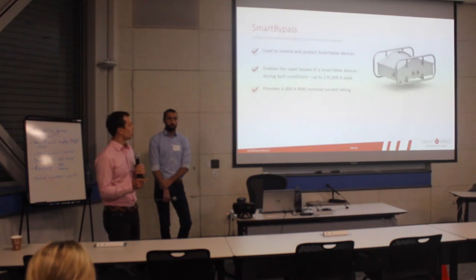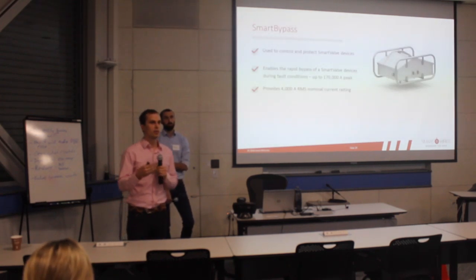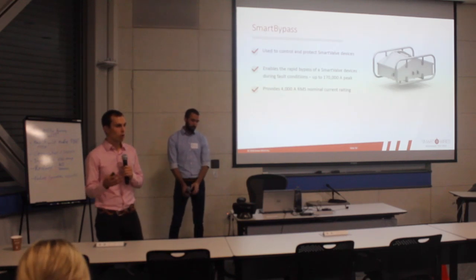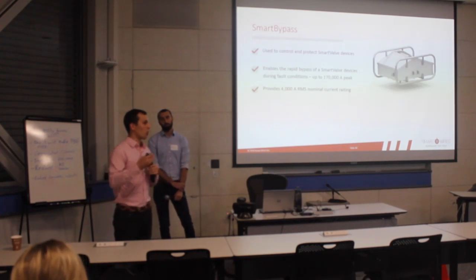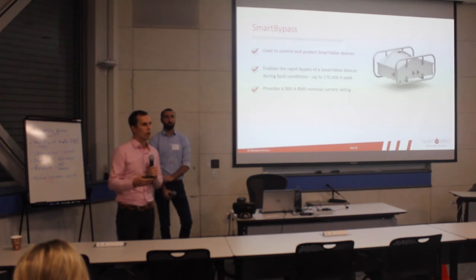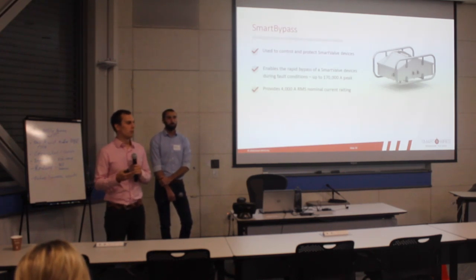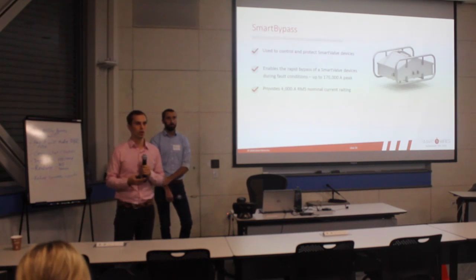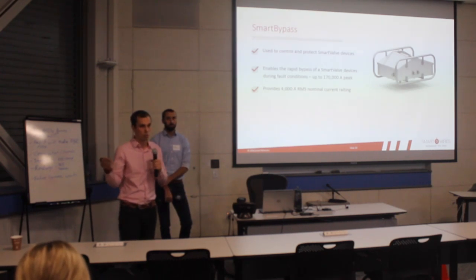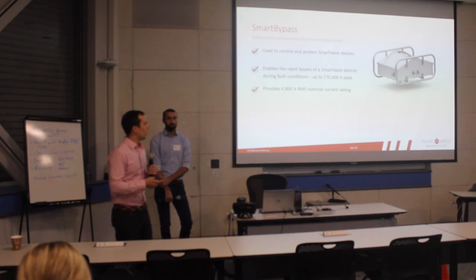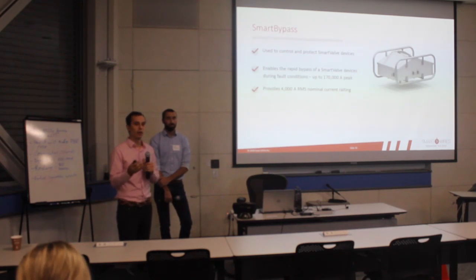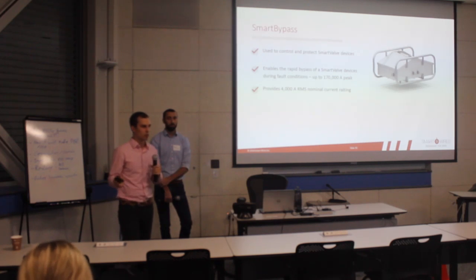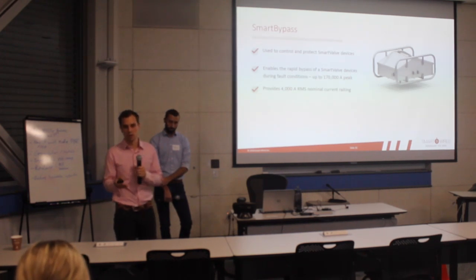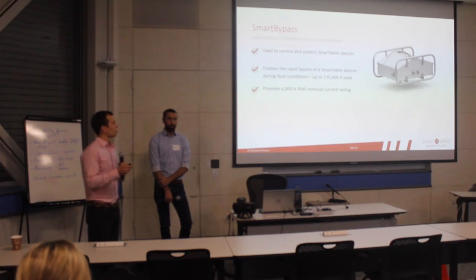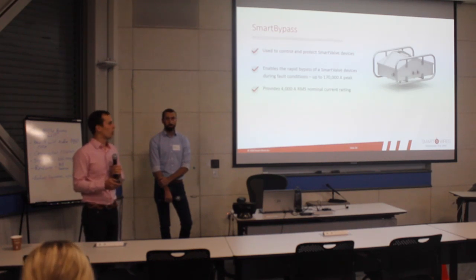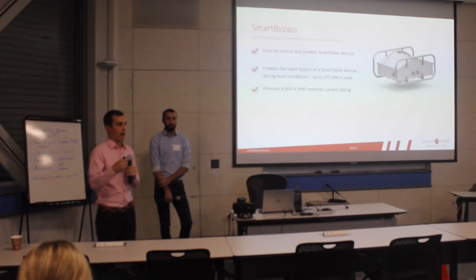The smart bypass is the device that protects the smart valve. So when that fault current comes, a lot of our engineering work and IP has been around how we handle that current when 170,000 amps are coming at our little power semiconductors, essentially what you'd put in an electric car. These two devices go together to provide the package that SmartWires is providing to the grid. That's a quick overview of the products and exactly what we're actually selling utilities.